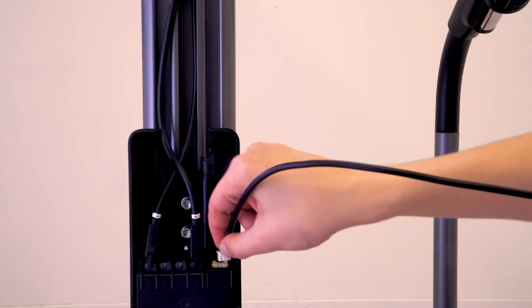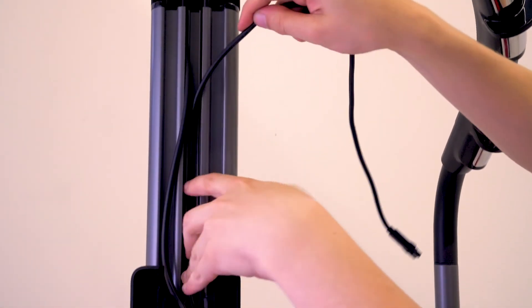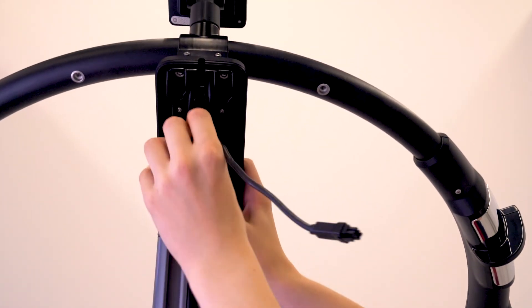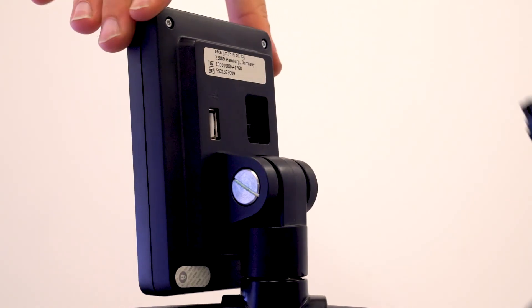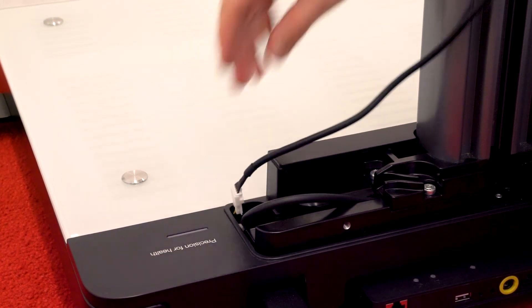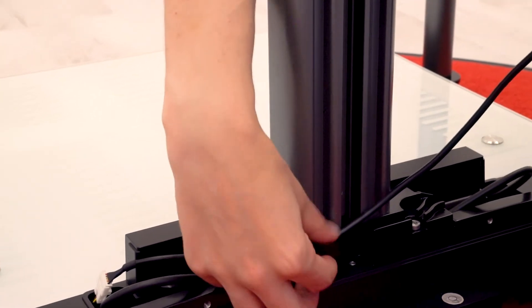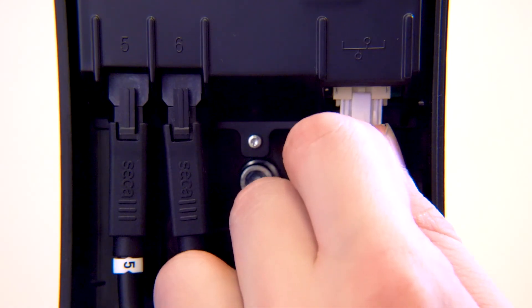Connect the longer connection cable to the seca device bus socket in the top right of the BIA box. Guide the cable through the cable duct of the column and the cutout of the handrail connector, then connect it into a socket at the back of the display. Connect the short connection cable into the remaining socket on the scale, then connect the other end to the seca device bus at the bottom right-hand socket of the BIA box.